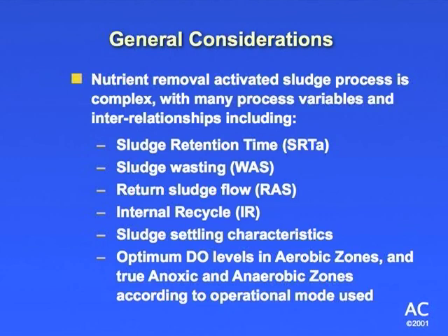And then sludge settling characteristics, in our case, these should improve, because of your nutrient removal processes, those selectors up in front. Because of their configurations, and especially with the high food to microorganism ratio right off the bat in the first selector, those selectors will help encourage better settling microorganisms. They found this out. It's tried and true. And also, when you're doing phosphorus removal, when you get the PAOs, when you have an anaerobic zone, those bugs really settle very well. Okay, so another great advantage of doing phosphorus removal biologically.